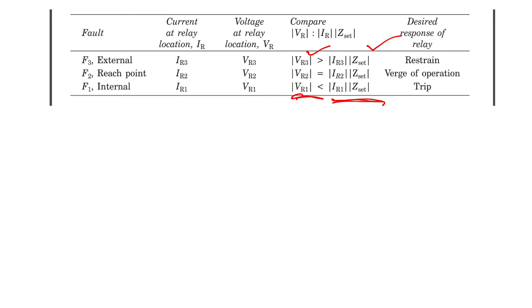The third one is IR1, which is the desired case, that is the internal fault, and if VR1 is less than IR1 into Z set, then it will definitely trip, as we have seen. So VR1, the voltage seen by the relay, is less than the current into Z set. When the voltage is less than the current into Z set, then it will definitely give the trip signal. This is also clear from this diagram.